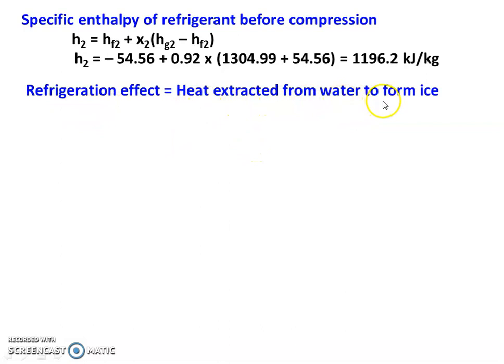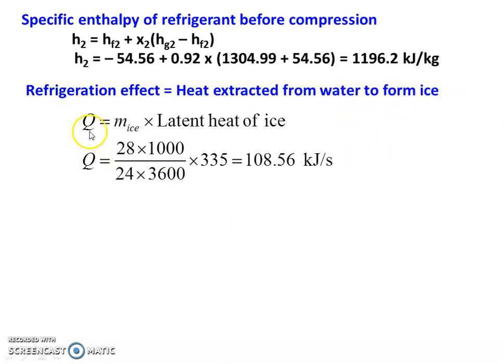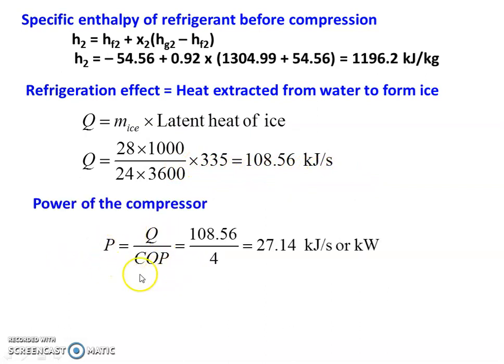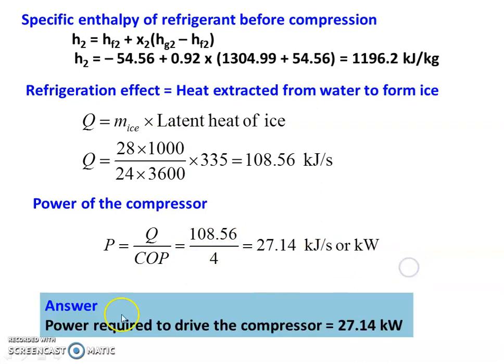The refrigeration effect equals heat extracted from water to form ice. Q equals mass of ice into latent heat of ice: 28 into 1000 divided by 24 into 3600, into 335 equals 108.5 kilojoules per second. Power of the compressor P equals Q divided by COP: 108.56 divided by 4 equals 27.14 kilojoules per second or kilowatt. The power required to drive the compressor is 27.14 kilowatt.